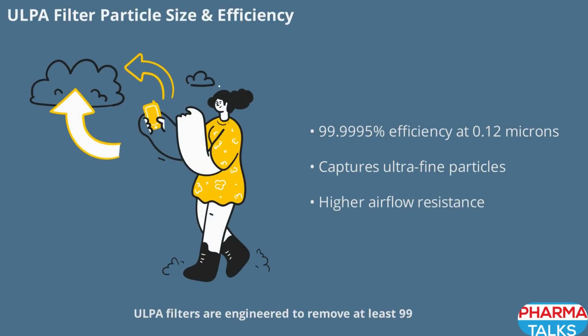ULPA filters are engineered to remove at least 99.9995% of particles as small as 0.12 microns. This remarkable capability allows them to capture ultrafine particles that even HEPA filters might miss. Such performance is crucial in environments where near-zero contamination is the goal. However, ULPA filters also create a higher pressure drop, meaning they resist airflow more than HEPA filters. This can impact HVAC system design and energy consumption, making it important to weigh the benefits against the operational challenges.